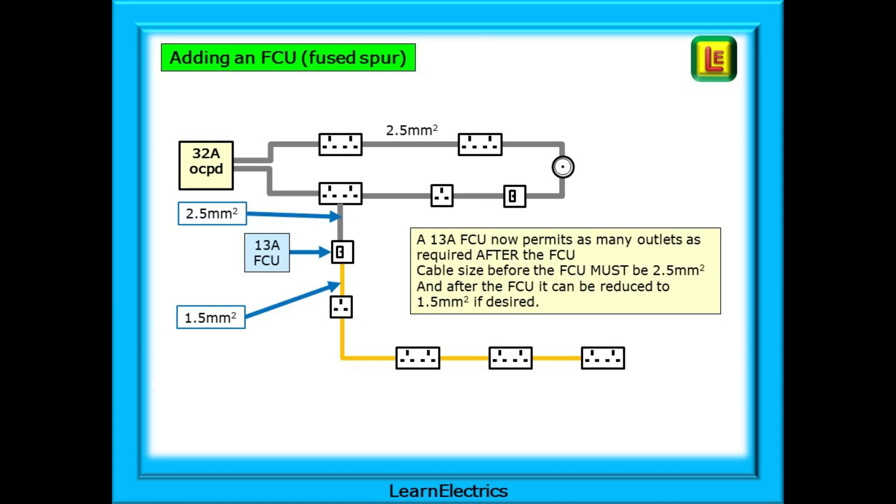Shown here, we now have a fused spur. Straight off the ring, we have a 13 amp FCU and we can put as many socket outlets as we need after the FCU. Look at the cable colours and sizes. From the ring to the FCU, it is 2.5 cable. After the FCU, it can, if we wish, be reduced to 1.5mm cable, shown orange here.